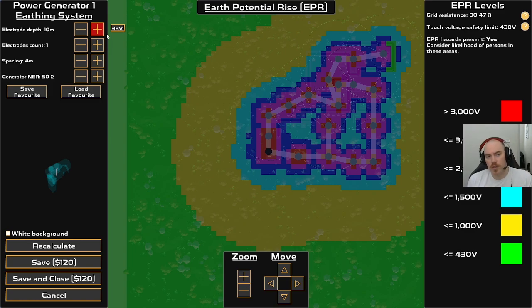So we need to look at ways to manage this. You can see here on the left, which is the power generator, we have five electrodes going into the ground. Essentially, if you get lightning, that lightning will go from the substation or generator into those electrodes and through the ground to dissipate out.